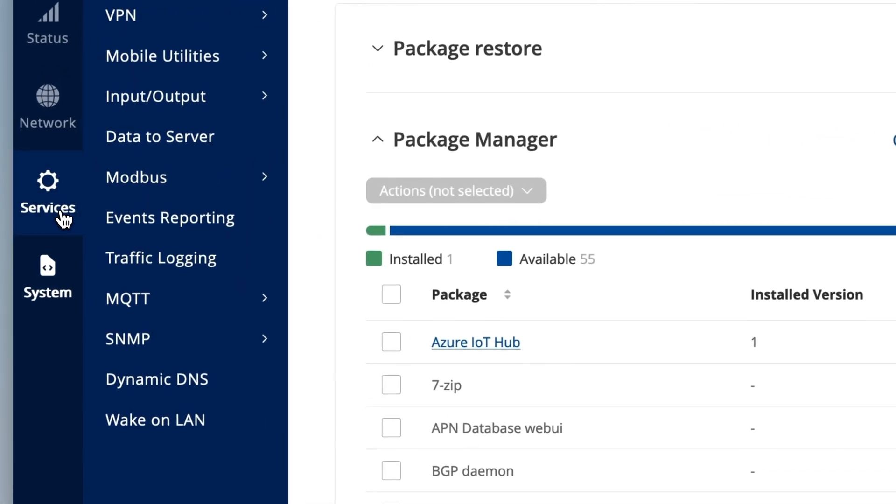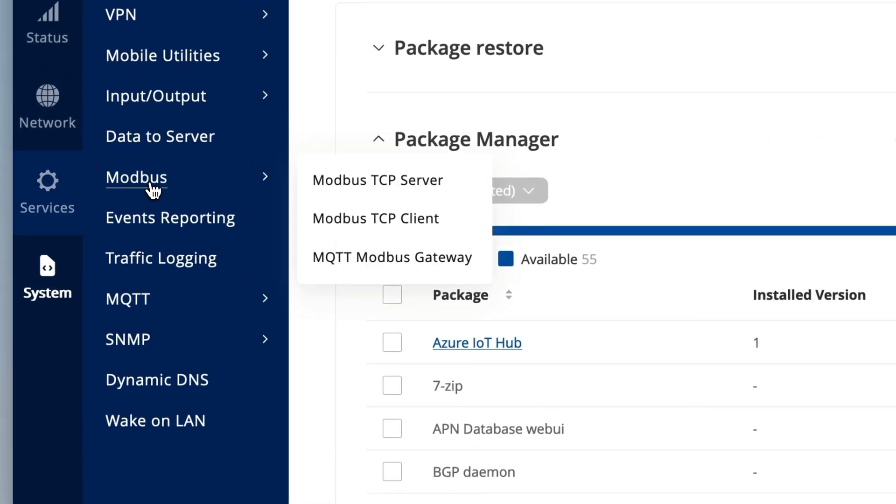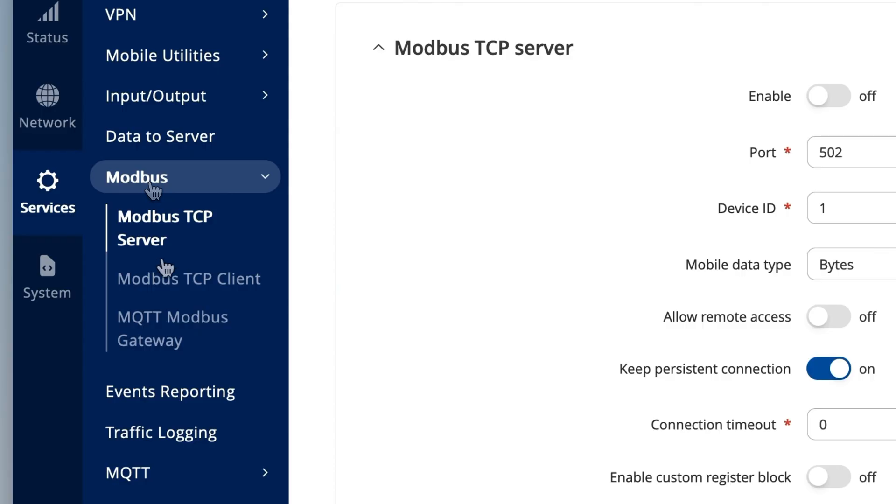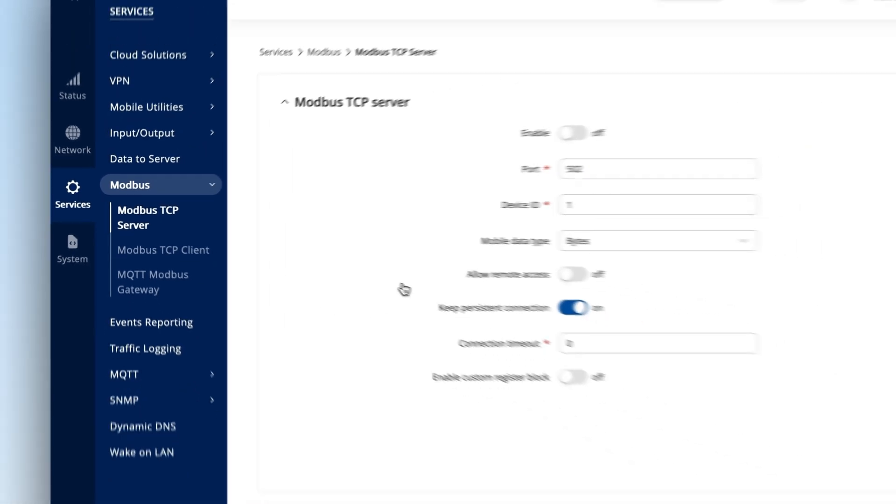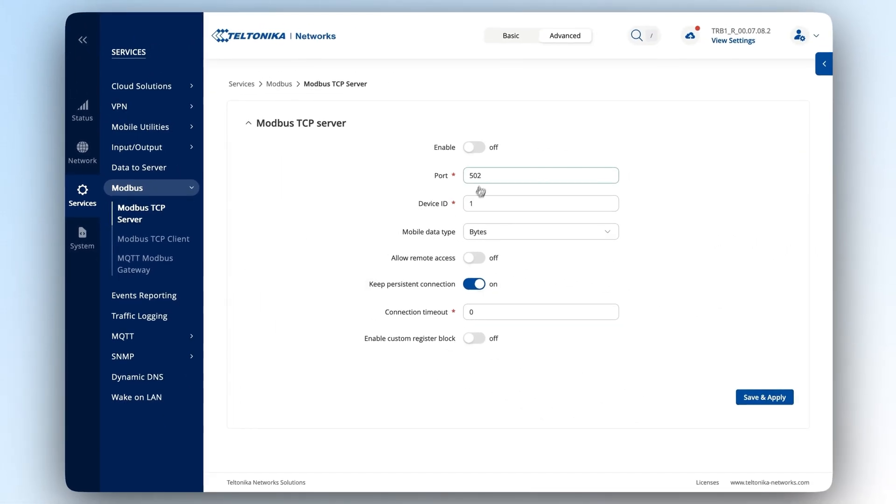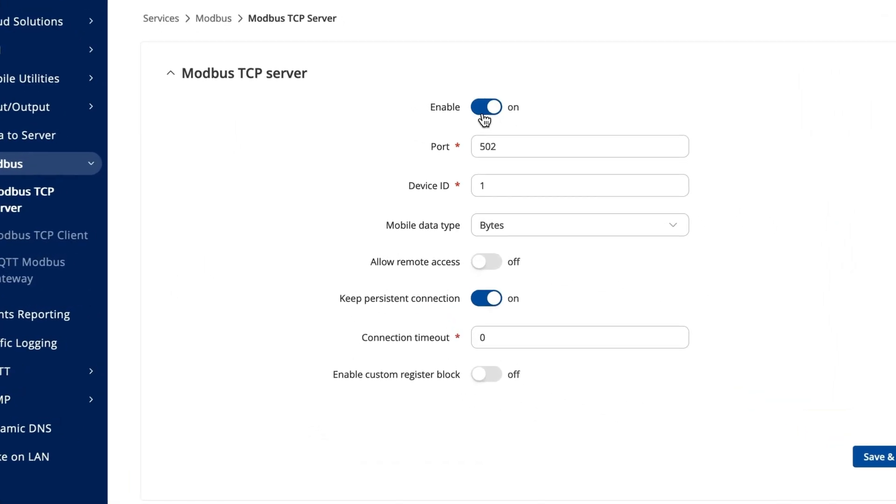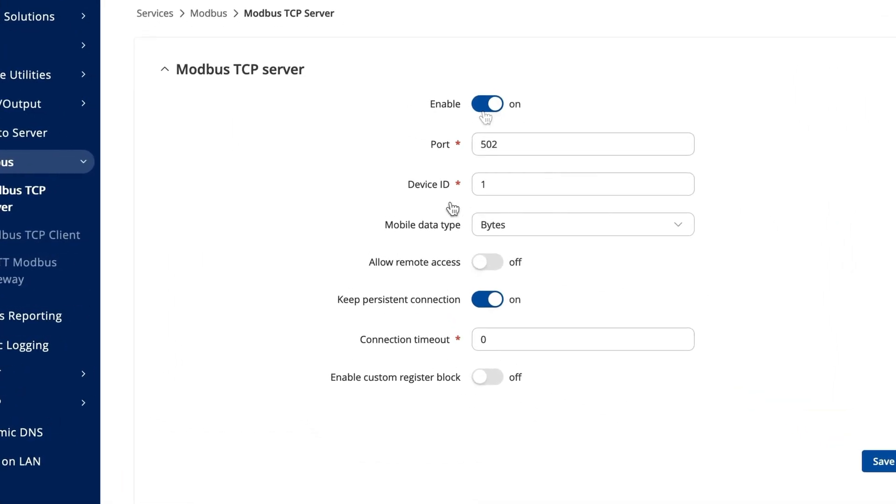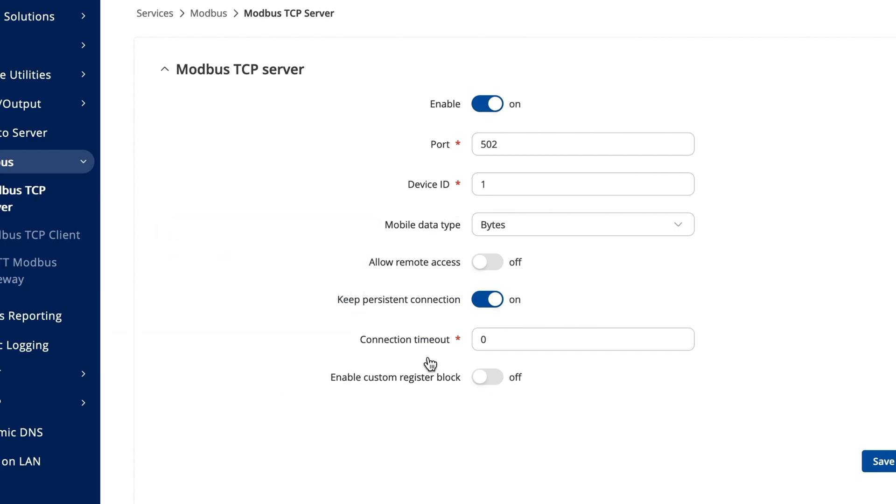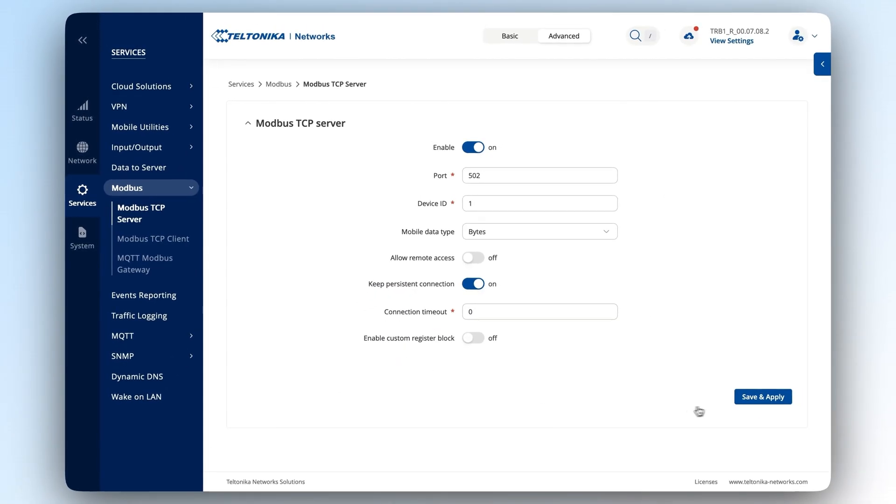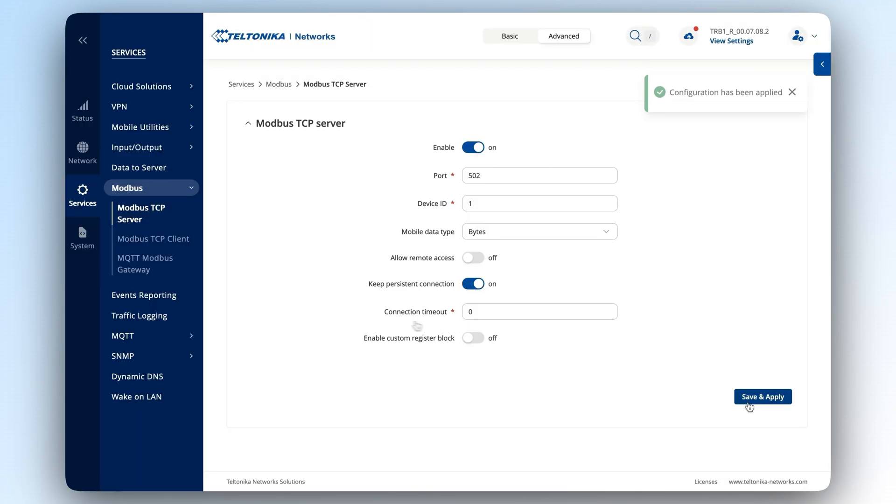Navigate to the Services section, select the Modbus tab, and open the Modbus TCP server page. The first thing you need to do is enable the Modbus TCP server. You can leave the default settings for port, device ID, and connection timeout. Press save and apply.